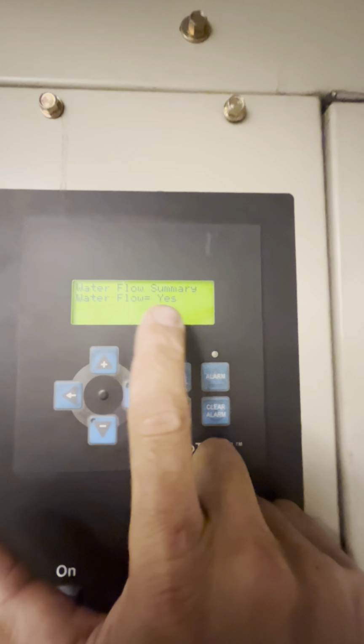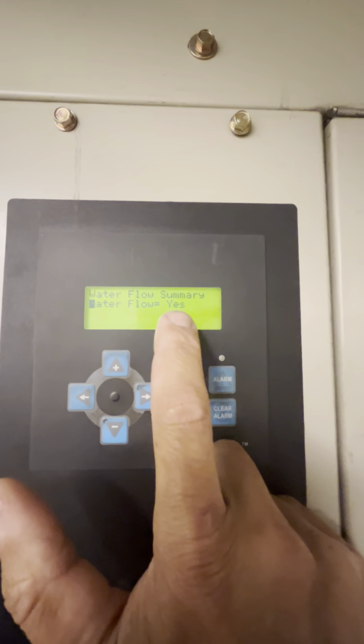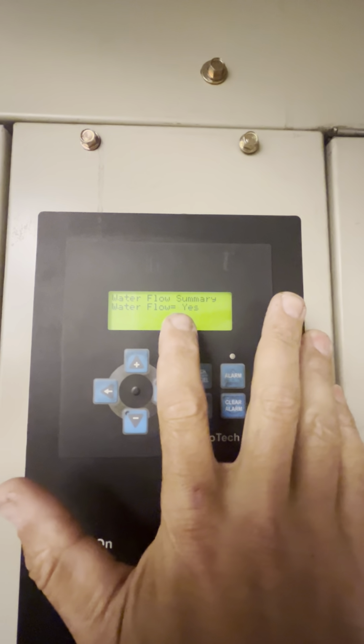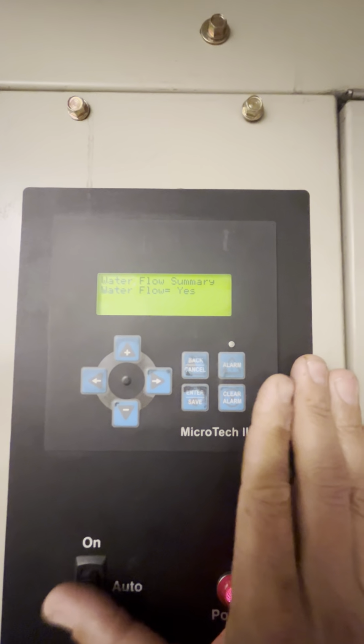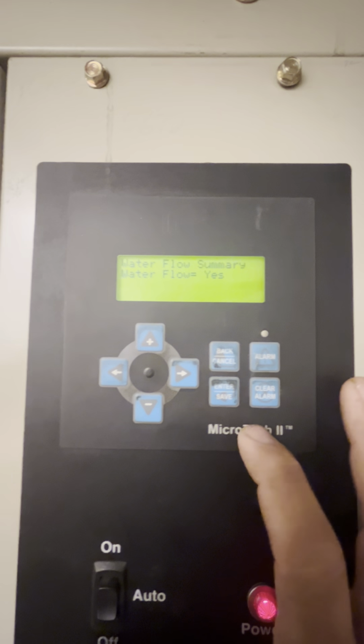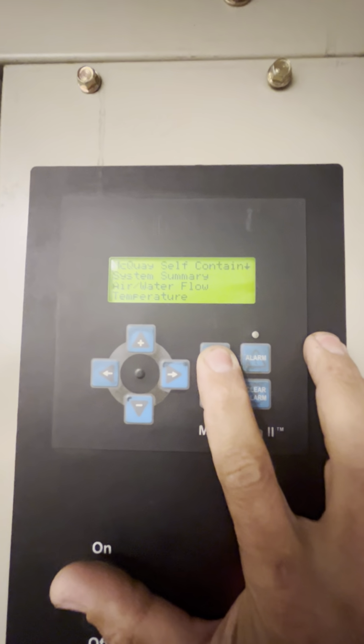Scroll over one more and you get your water flow. That needs to always be yes. If you're having issues with high pressure, always come and check that water flow. If that says no, you have an issue maybe with your pump or with the cooling tower, but this unit will not run if water flow is no, because it has nothing to cool the machine down. We'll go back to the main screen.